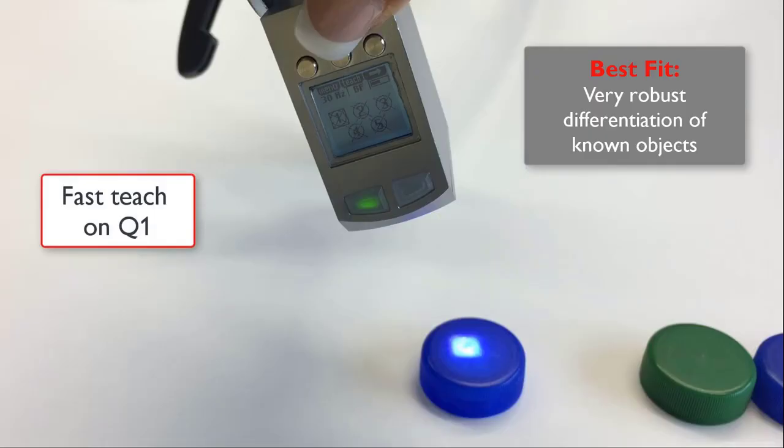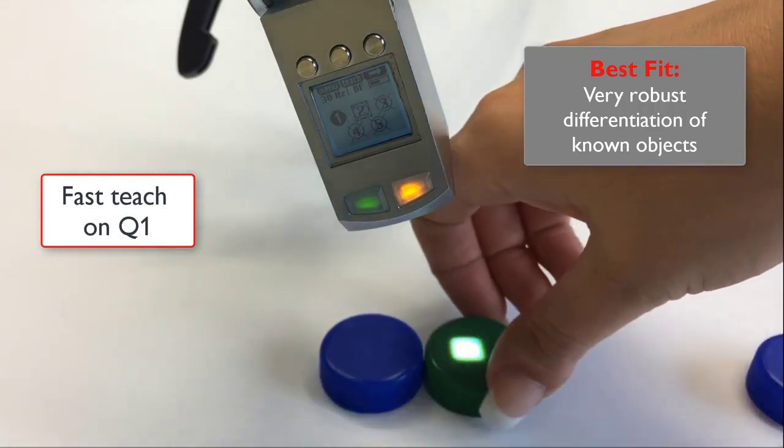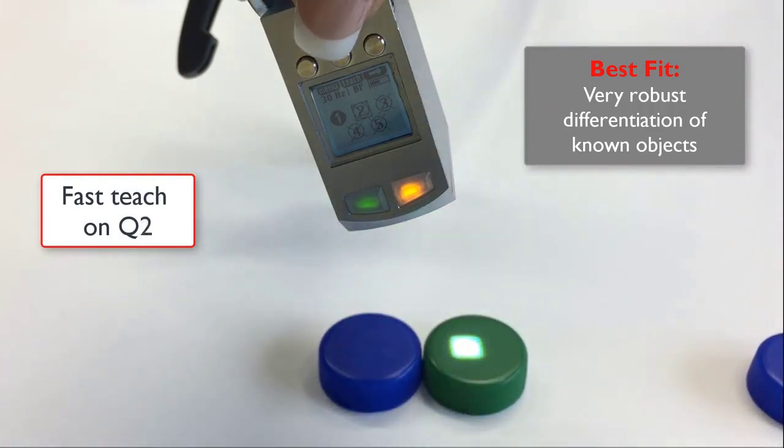Here's an example. We'll check the color of different bottle caps. Here we'll quick teach the blue one by pressing and holding teach for more than three seconds. Then we'll tap next. Teach color two, we'll press and hold for more than three seconds. We've taught green.